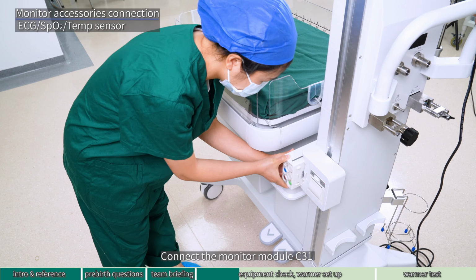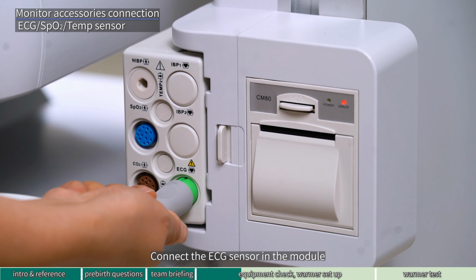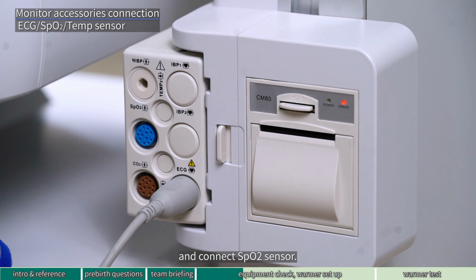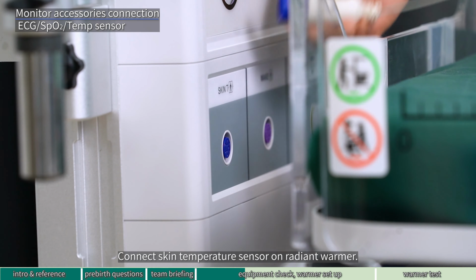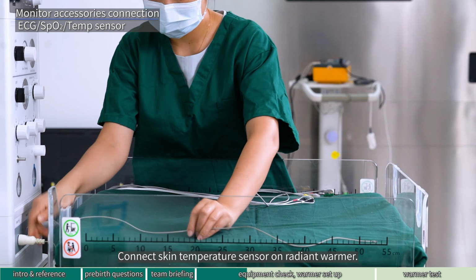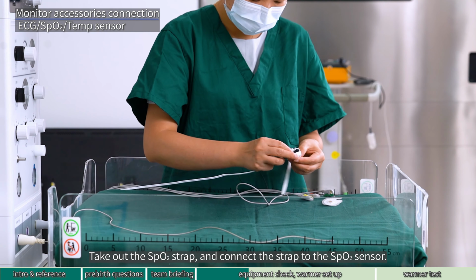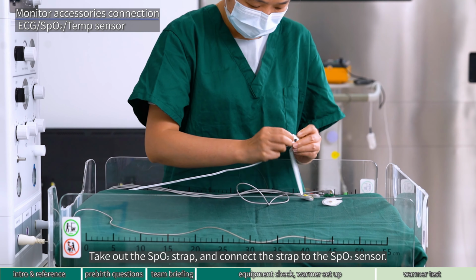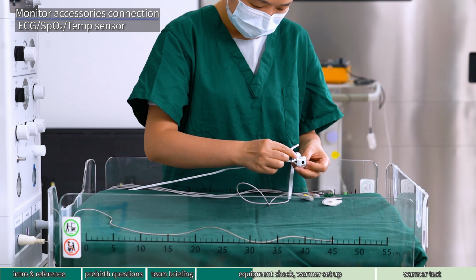Connect the monitor module C31. Connect the ECG sensor in the module. And connect SpO2 sensor. Connect skin temperature sensor on radiant warmer. Take out the SpO2 strap and connect the strap to the SpO2 sensor.